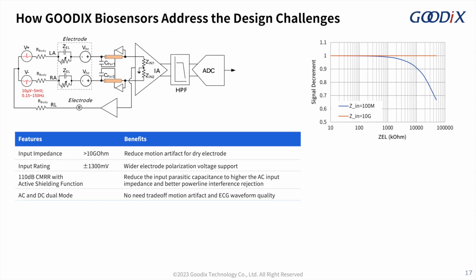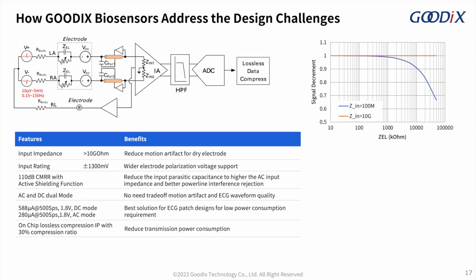Support for AC and DC dual modes. Engineers don't need to trade off motion artifact and ECG waveform quality. Low power consumption at 500 Hz sample rate: DC mode is 588 microamps, and AC mode only needs 280 microamps. Integrated lossless compression IP, 30% compression ratio, which can greatly reduce the power consumption for data transmission.